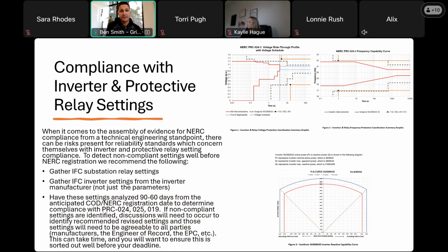Second thing I wanted to cover is trying to determine compliance with your inverter settings, your protective relay settings. These are standards like PRC 24, PRC 25. When we go through the development and implementation of a NERC compliance program for a generator owner, we generate evidence for these standards so your program is audit ready, and we demonstrate compliance with these various standards. The standards that can result in non-compliant findings are the ones I just mentioned, associated with relay settings and inverter settings.